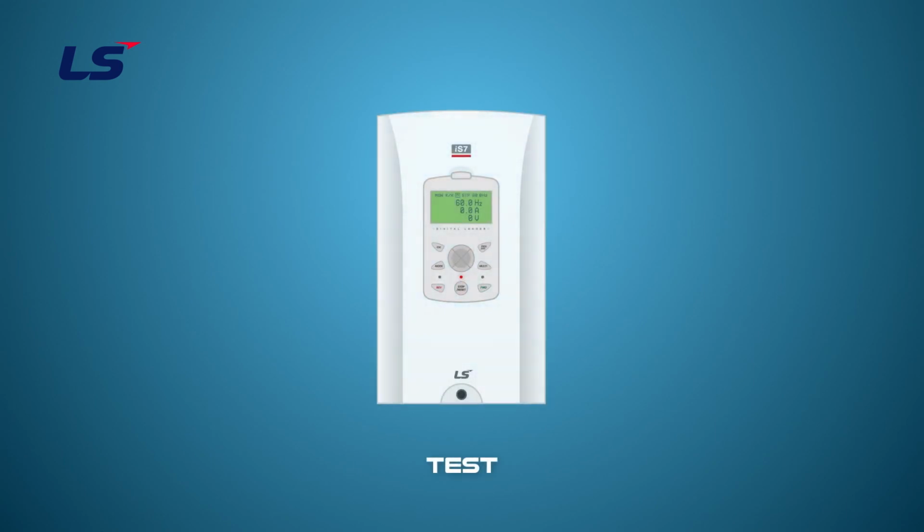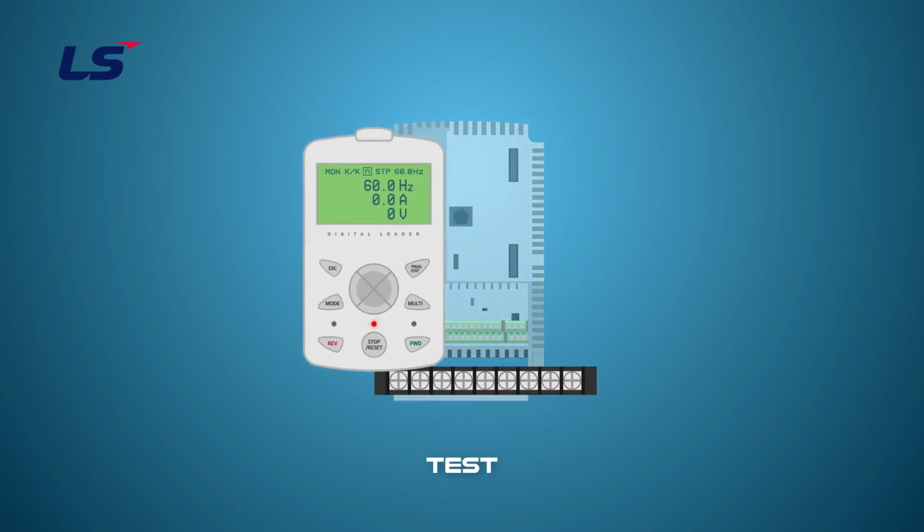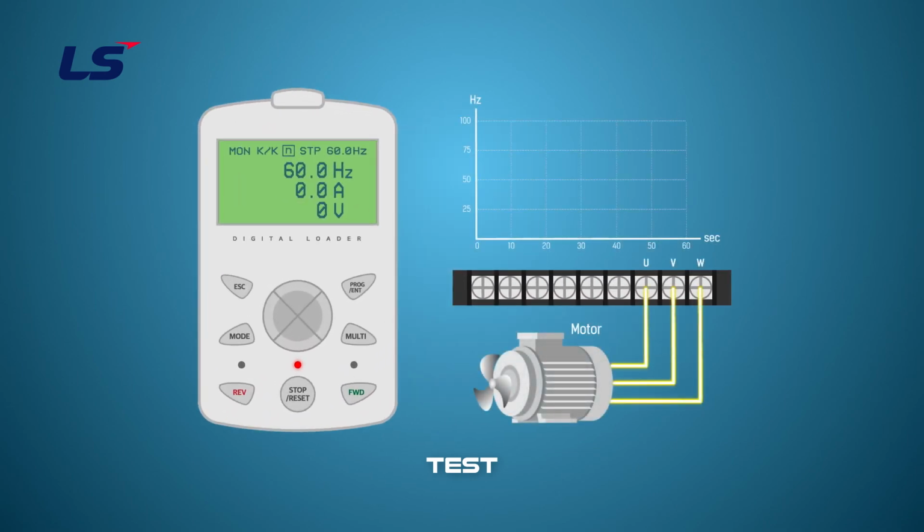So far, the basic parameter settings are complete, and we're going to run the motor. Looking at trend waveforms, keypads, and motors, you can see that it takes 10 seconds to accelerate to 60 Hz, and 10 seconds to decelerate from 60 Hz to 0 Hz.